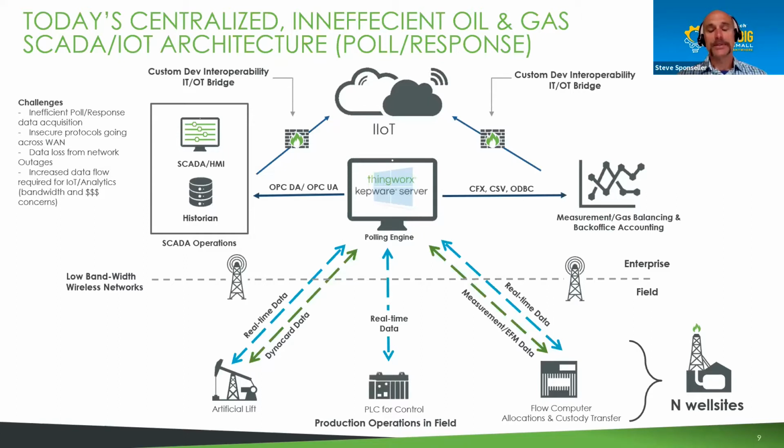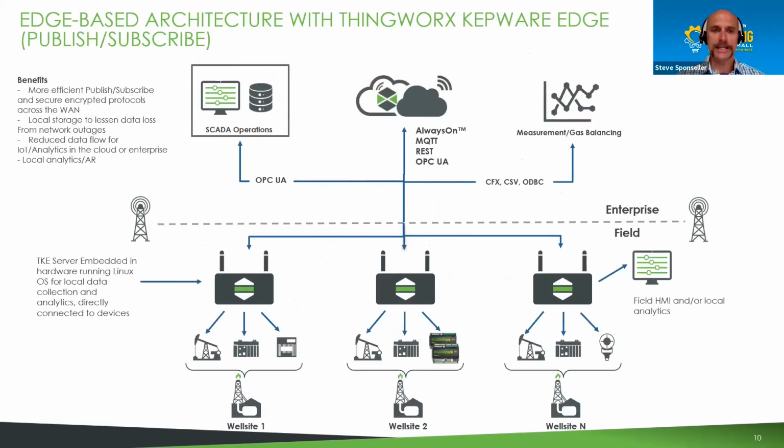And with just typical SCADA purposes, it's barely able to get all that data that's needed. Sometimes SCADA data could be 1 minute data or 5 minute data, depending on how critical that data point is. But if you're trying to build machine learning models to do all the wonderful stuff that advanced analytics promises, you need much more frequent data to be able to do that. And that's just something that's not possible with this architecture. So that's what brings us to the edge.